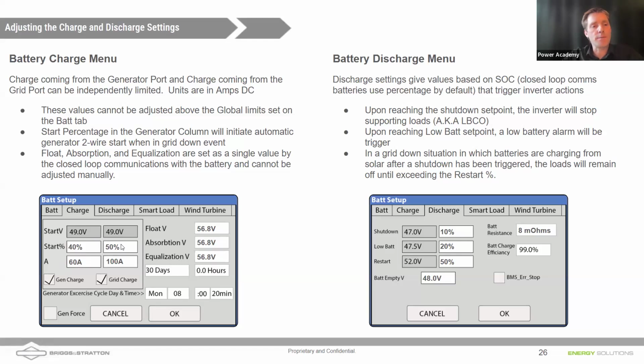On the other side of things, if I am allowing charge by having this box checked on the grid side of things, then once I'm below 50%, it would initiate a charge cycle if the grid is available. So it would only use this generator charge cycle if the grid is unavailable. So keep that in mind.